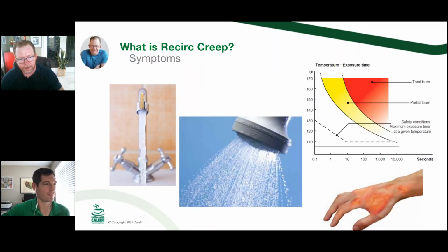The other thing we want to have a conversation about is recirc creep. So recirc creep has some symptoms. Obviously, the number one thing we're trying to prevent is the gruesome burns that you can potentially get. Basically, what's happening when you have recirc creep is it's long periods of time where there is very little domestic hot water demand. And so what'll happen is the first person that gets up and cracks that tap, they're the ones that are getting that blast of hot water that can potentially result in scalding to whoever turned that tap on.